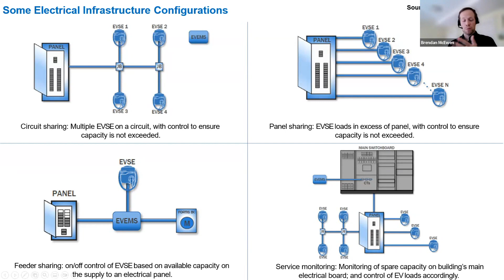The advantage is that it significantly reduces the cost to provide an EV-ready outlet in these buildings. This is a costing study done with my previous employer, AES Engineering, in 2021 for Clean Air Partnership. For this particular high-rise building, if you did things without any energy management on 40 amp circuits, you're looking at an incremental cost of about $5,500 per parking space, which is pretty expensive.